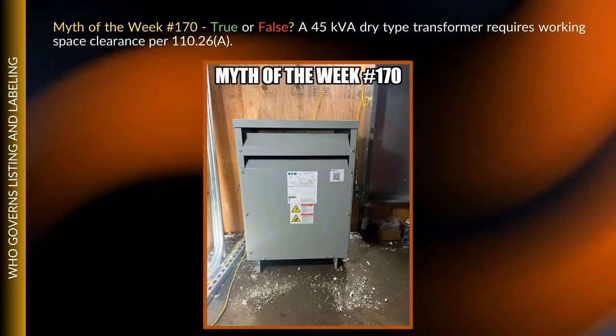All right, so let's take a peek at what we have here. 110.26, spaces about electrical equipment. What I've noticed is that when you have a code section with multiple subsections, A, B, C, D, E, a lot of people want to skim through and figure out which one applies to them, and they only read that. You need to make sure you're reading the language before the A, B, C, D - what I kind of call the charging language to that section. So 110.26, before you get to A, has this general requirement, and it applies to all equipment.